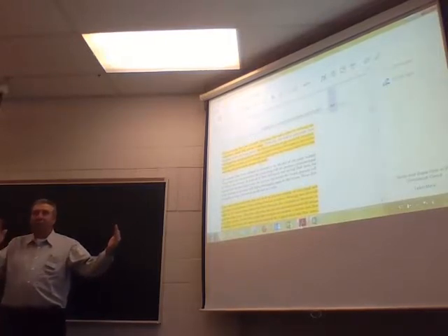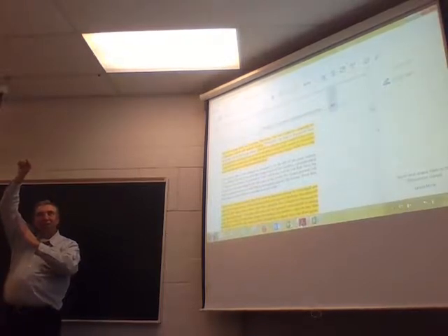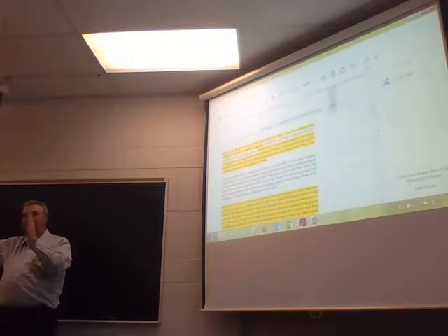As long as my flow is going this way, everything's tickety-boo. As soon as the flow starts to drop, just before I get a surge back, it opens a vent line and makes that surge go out, so it doesn't come back on my compressor. If it's a toxic gas, it takes that surge line and instead of the atmosphere, it takes it over to the inlet side. All right, got that?